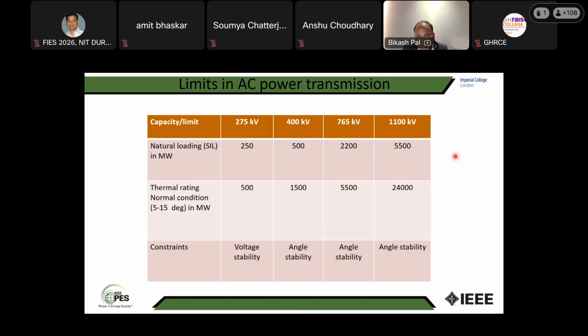Why angle stability? Because the line length is long. So for every kilometer, there will be an angle difference, so you have a large angle difference. And with the large angle difference, your operating point in the power angle curve moves towards the peak value of the power angle curve. So these are the constraints for power transmission in the AC line.